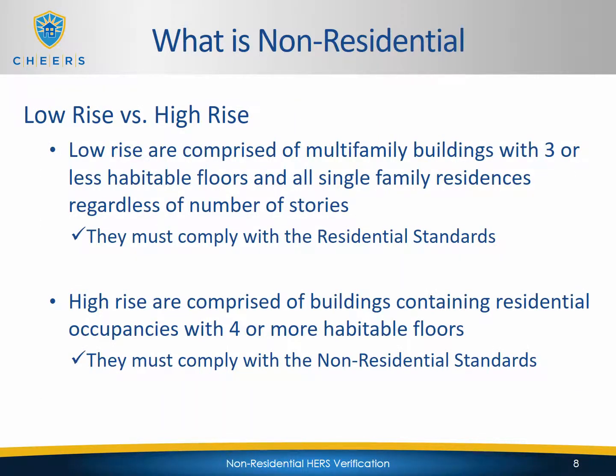What is the difference between low-rise and high-rise residential buildings? Low-rise comprises multi-family buildings with three or less habitable floors and all single-family residences regardless of the number of storeys — these must comply with the residential standards. High-rise residential buildings contain residential occupancies with four or more habitable floors and comply with the non-residential standards. Three or less floors is low-rise; four or more is high-rise.